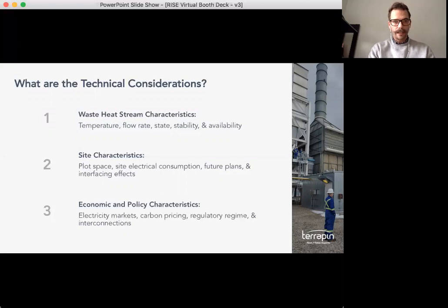And the flow rate is highly dependent on the temperature. For example, at 463 degrees Celsius, we would need around 82 kilograms per second in flow rate of the waste heat resource to be able to generate power. As that temperature drops, the flow rate requirement goes up if we want to create power.